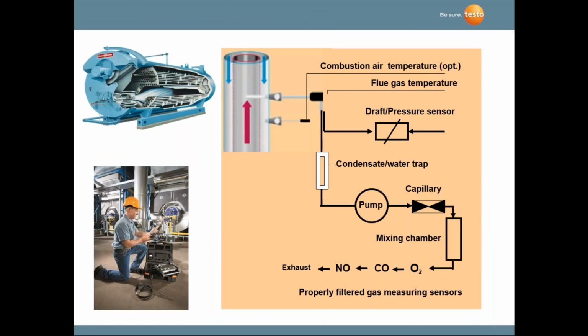I bring this to your attention because in a combustion analyzer, and in a Model 300, we're pulling a sample of flue gases from the tip of the probe through a probe tube that's about 13 inches long, through a hose assembly that's 7 to 8 feet long. And then it goes into the analyzer, where the flue gases are filtered and the water is taken out of the flue gases. And the last place the flue gas goes is into the oxygen, carbon monoxide, and NO sensors before it's exhausted out of the analyzer.